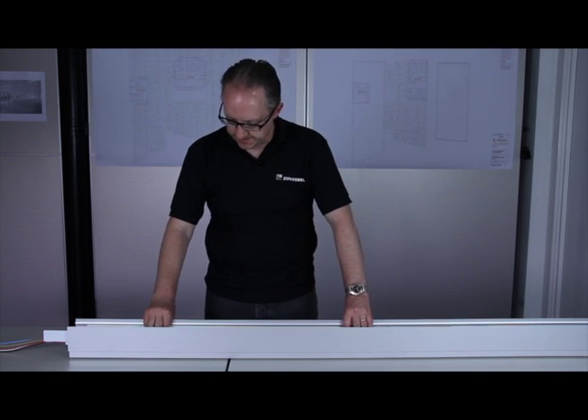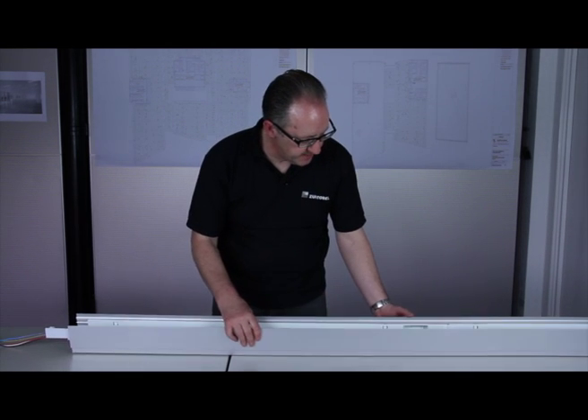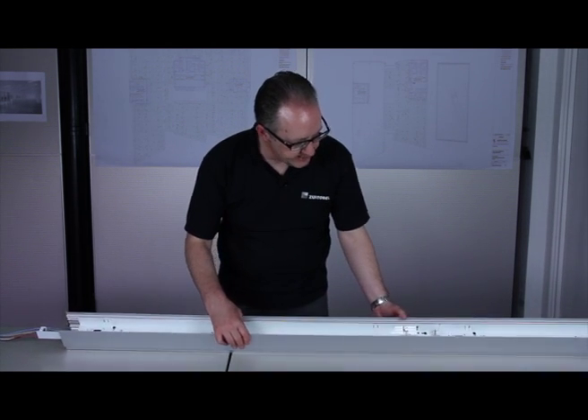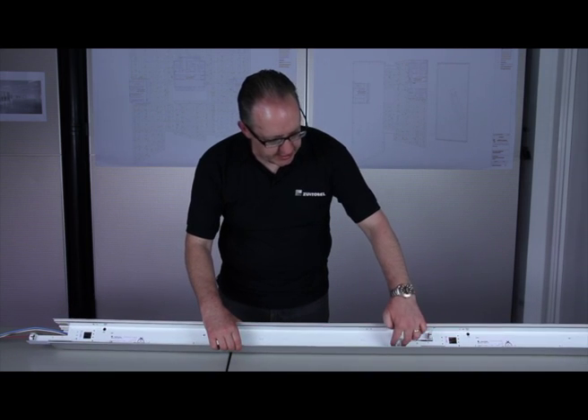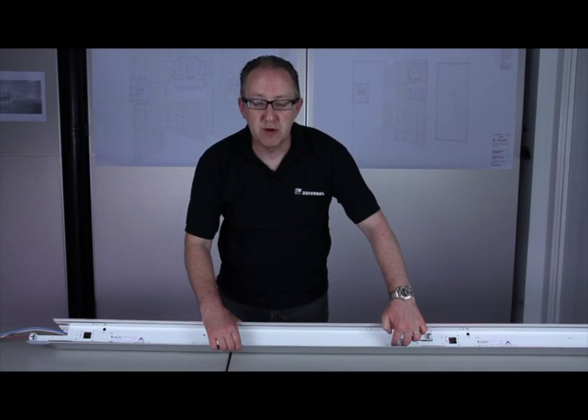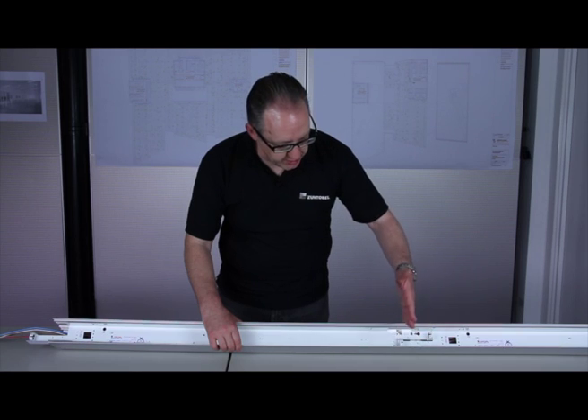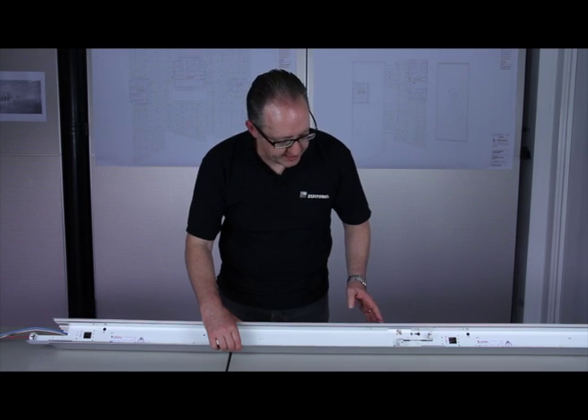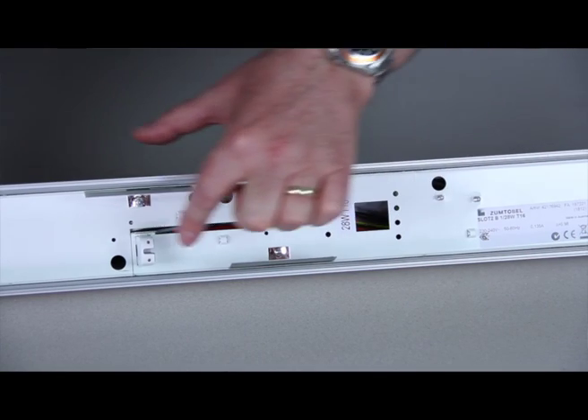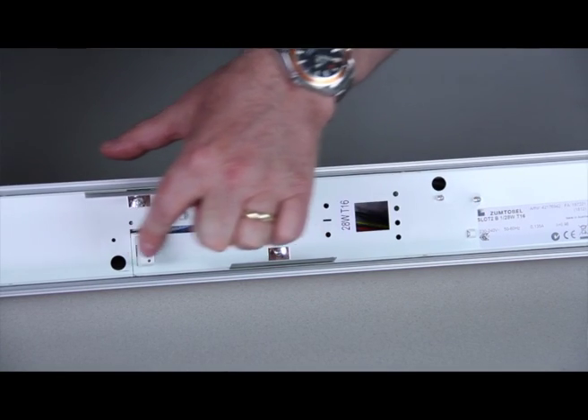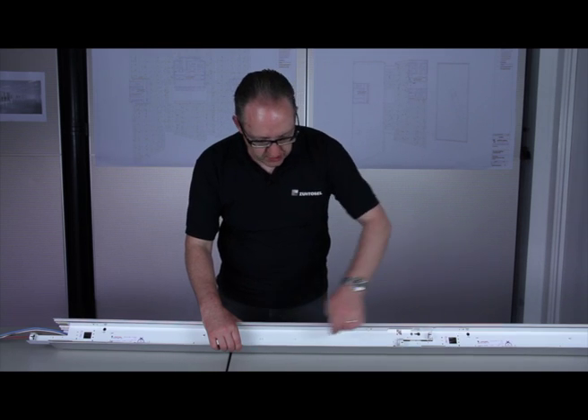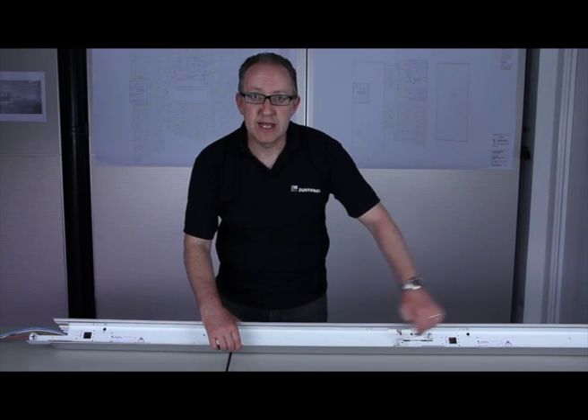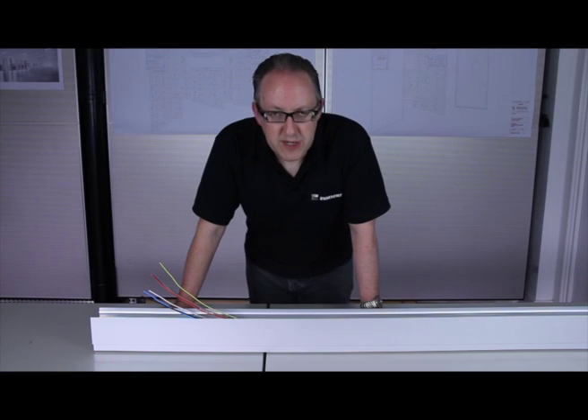Two clicks. What's important here is that the gear trays are butted up tight together. In this situation with the fluorescent version, the fluorescent lamps overlap, and it's important to make sure the white reflector of the gear tray is continuous.